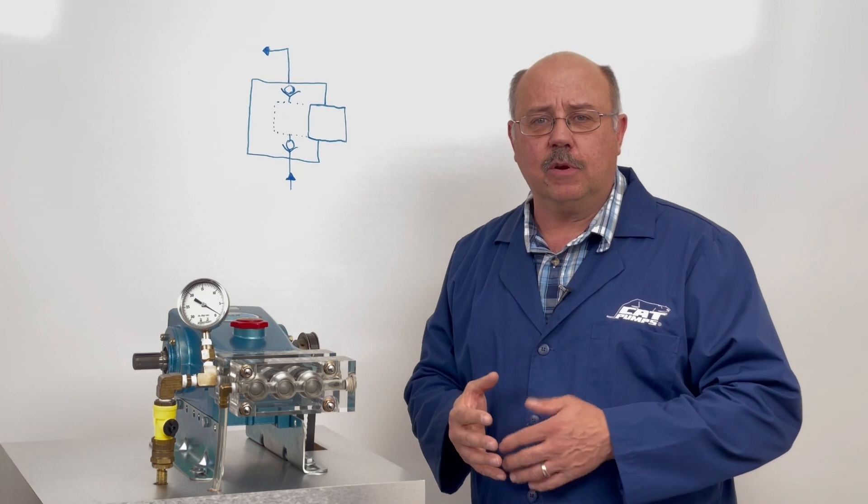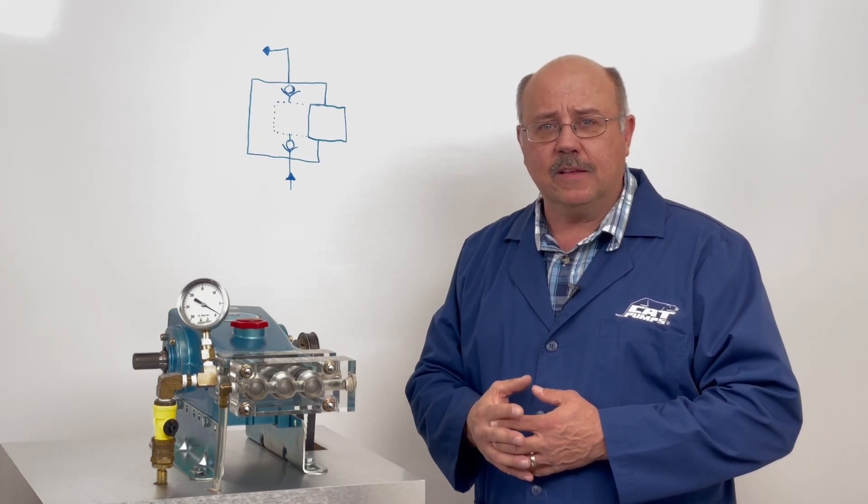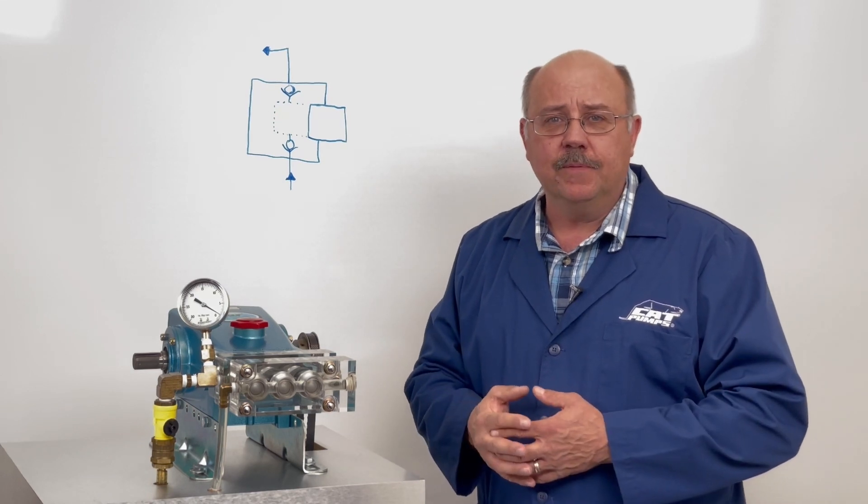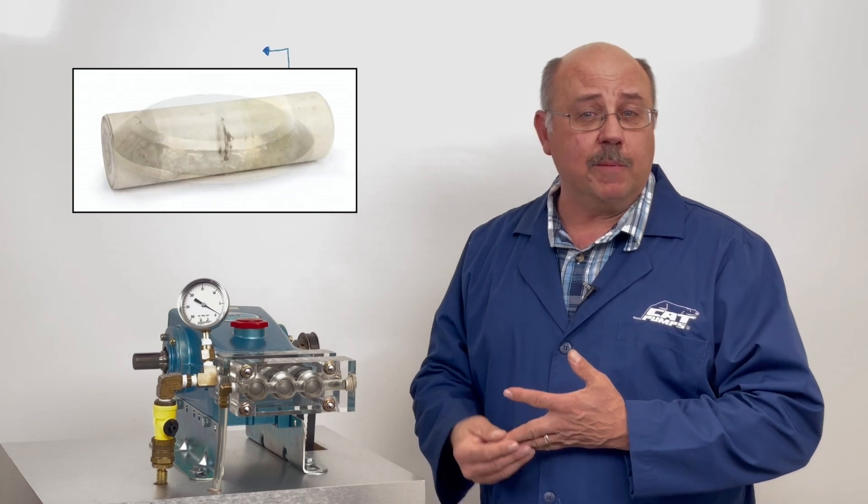And this cavitation creates a very violent force, and this force has enough power to chip away at surfaces like your valves, and your seats, and your ceramic plungers.